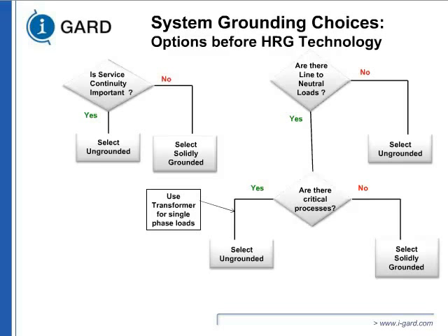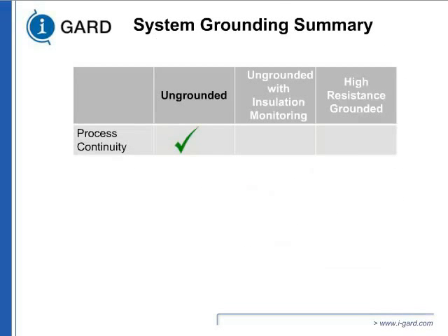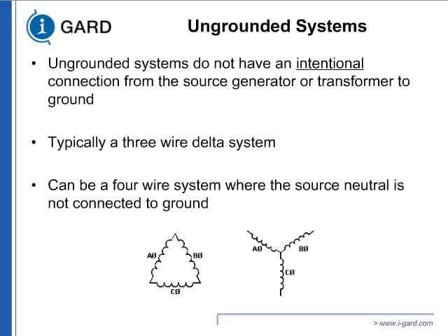This was the chart we went through, and if we have critical processes, then we put an isolation transformer or specialty transformer for single-phase load, and we connected the delta system to design most of our systems. Solid grounded was the last resort, as long as it doesn't affect the continuity. So if process continuity is required, there was only one option at that time, ungrounded system. And what is the ungrounded system? Ungrounded system does not have an intentional connection from the source to the ground. Key part is intentional. Typically it's a 3-wire delta system, delta-delta transformer, or sometimes you can have a 4-wire system where source neutral is not connected, but very unusual. Mostly you see delta-delta. And keep it in mind, the underlying part is the intentional connection.